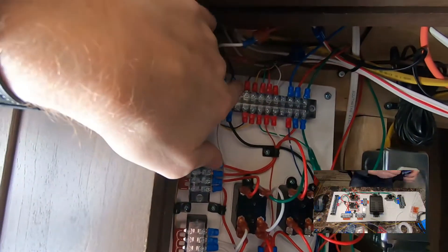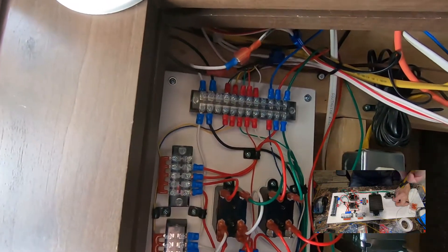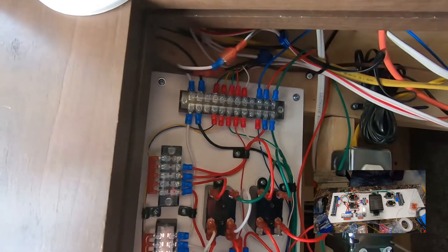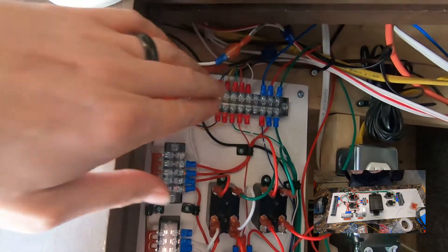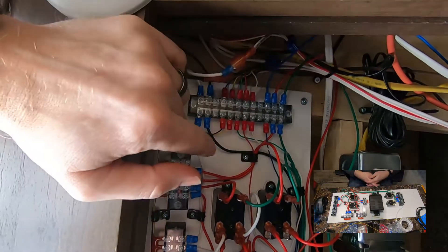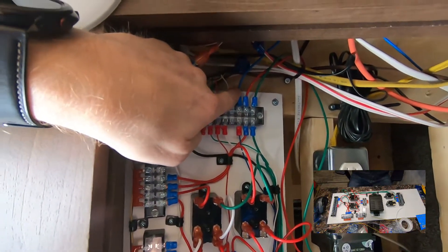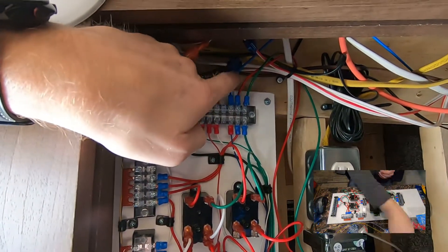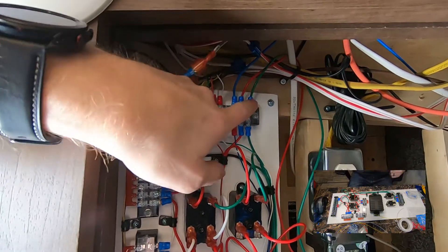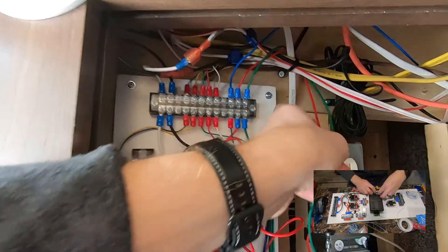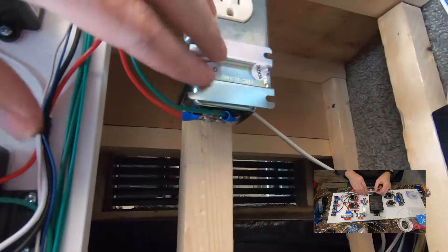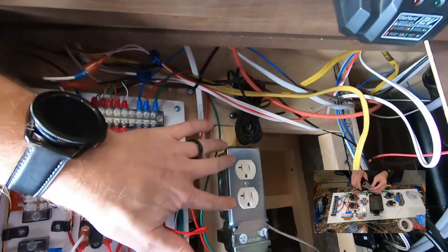And then I've color matched my wires: blue, yellow, green, red, and white. So that is a five wire thermostat wire, 18-5, and so that's running up to the thermostat. And then this end, the blue up here is going to the furnace thermostat control wire, and then my red and green come down here and they're attached to just a doorbell transformer right here which is hooked into this 120 volt line.